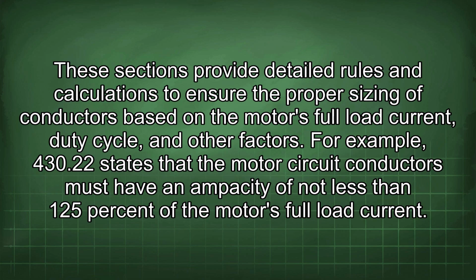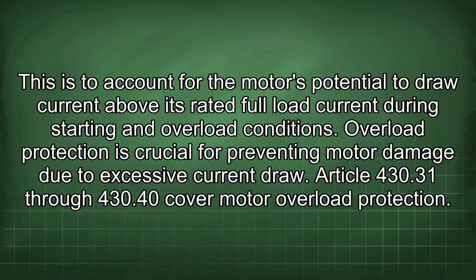For example, 430.22 states that the motor circuit conductors must have an ampacity of not less than 125% of the motor's full load current. This is to account for the motor's potential to draw current above its rated full load current during starting and overload conditions. Overload protection is crucial for preventing motor damage due to excessive current draw.